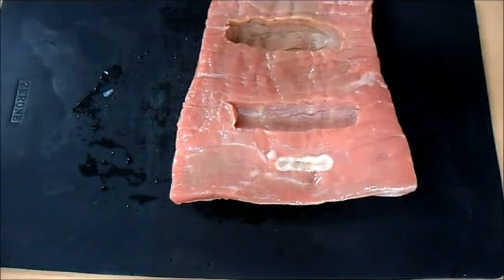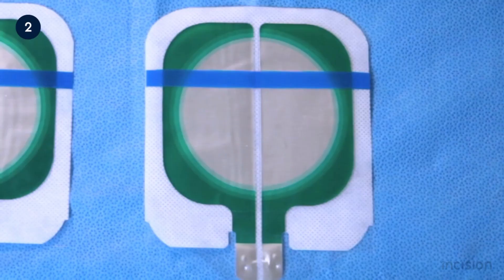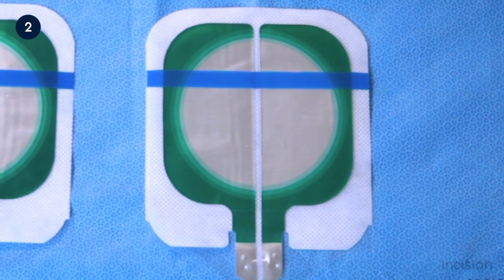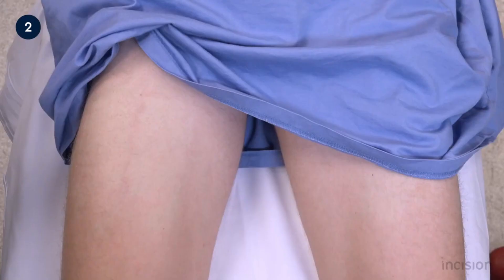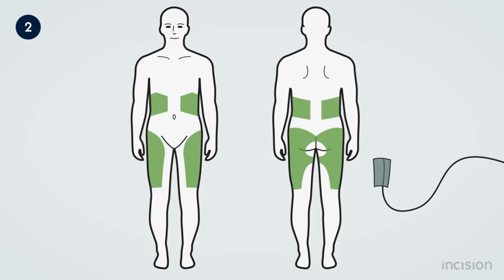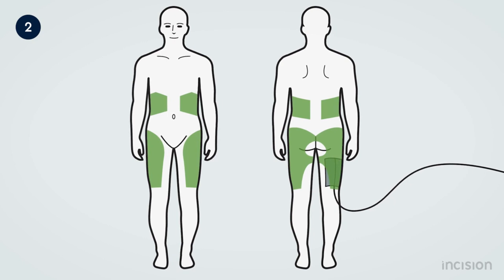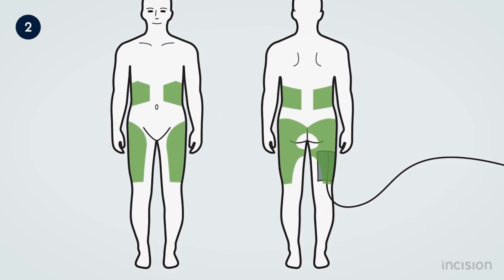There are two types of grounding pads in ESU: disposable and reusable. Disposable grounding pads are made of a plastic base material covered with a metal film that serves as the actual electrode surface. Covering the metal surface is an adhesive gel layer that can easily be attached to the patient's skin. Also referred to as single-use or sticky pads, the disposable grounding pad must be large enough to keep the current density low to prevent heat buildup that might result in a burn under the pad. Although cost-effective and versatile, disposable grounding pads can cause patient skin problems such as hypersensitivities, allergies, and even removal of layers of skin when the pad is removed. Additionally, many practitioners are concerned with the wastefulness of disposable pads. Advanced technology has introduced the reusable pad that reduces, and in most cases eliminates, the negative results of using disposables.